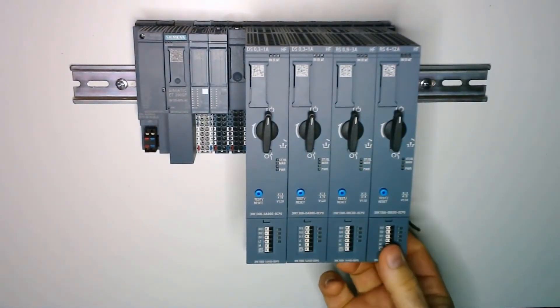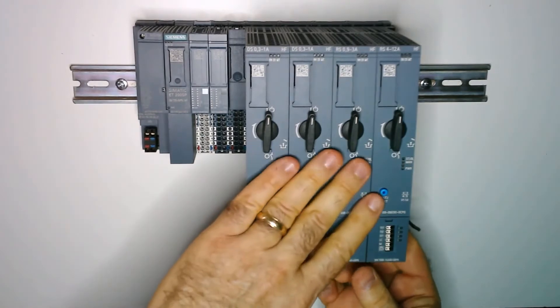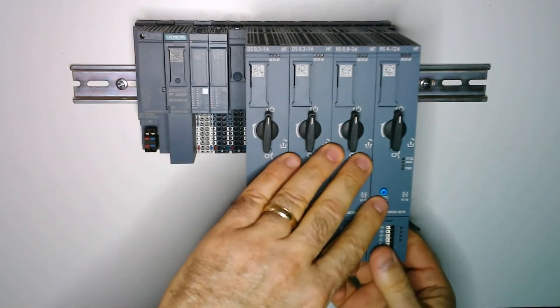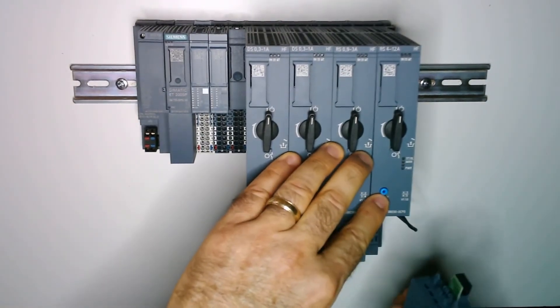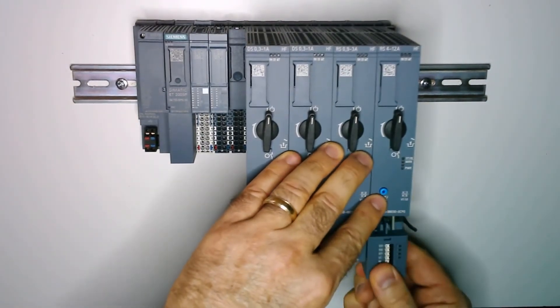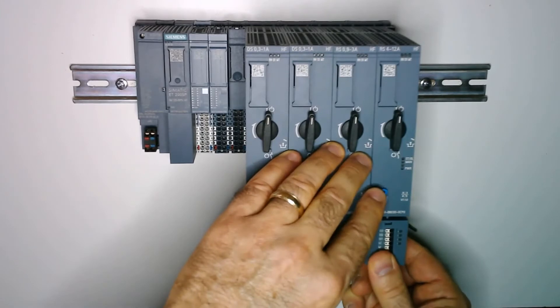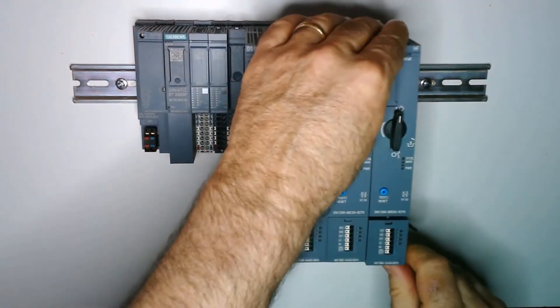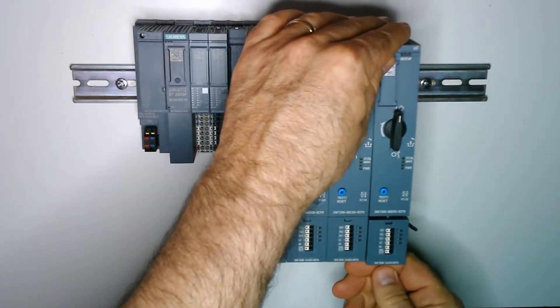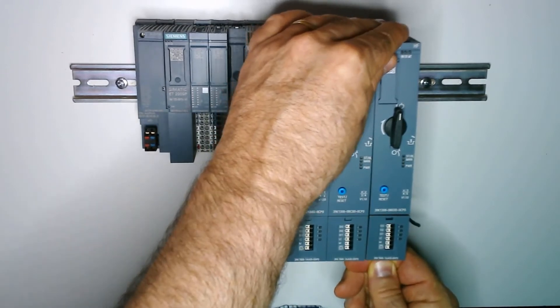I have installed an optional digital input module on each of the starters. This could be used for bringing push buttons or selector switches from the panel directly into the starter and therefore directly into the CPU as IO. This could save you the cost of an IO module.